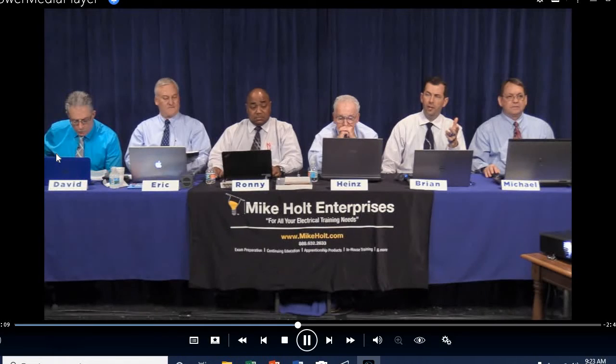Brian? Well, also, if you need to change phase rotation in a motor disconnect, inspectors are like, yeah, you can't do that. You've got to do that at the panel because it's got to be ABC. And I'm like, well, wait a second. That has nothing to do with this. That's the panel. That's just so you know how the buses are arranged in the panel. Oh, I see. You're trying to tell me that an inspector wants the black, red, blue, and he wants to make sure that that's an A phase, a B phase, and a C phase. In the disconnect, he wants it black, red, blue. Right. But the thing is, I needed the motor to run backwards for the equipment. So you just changed the two phases so it's black, blue, red.